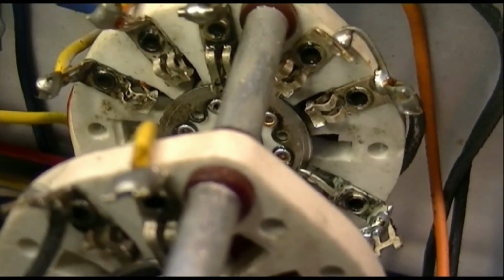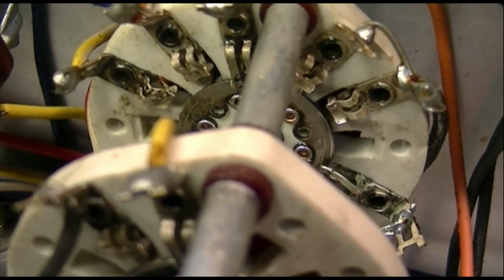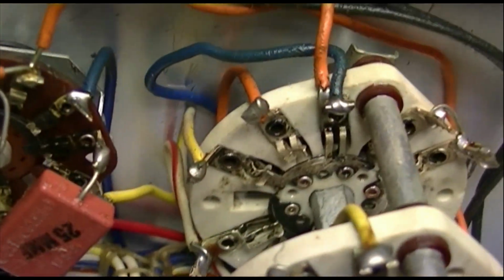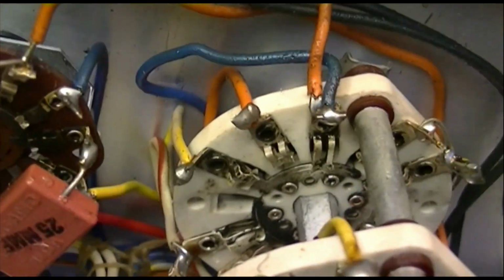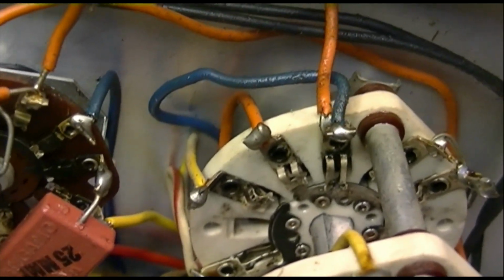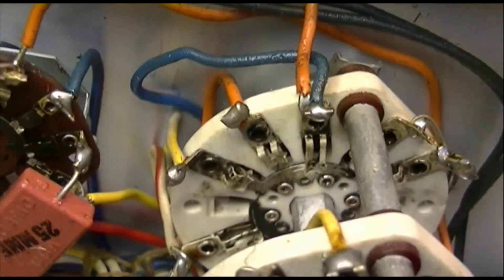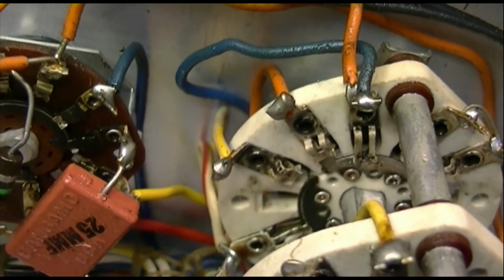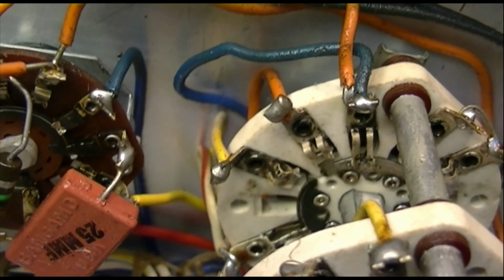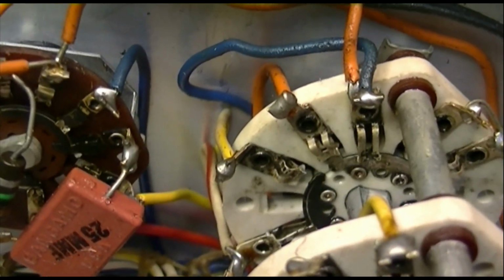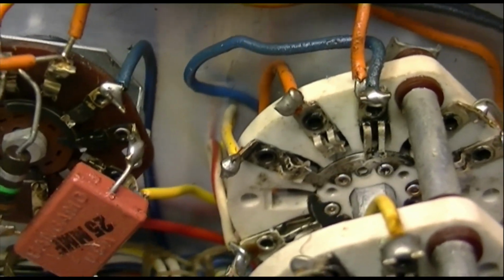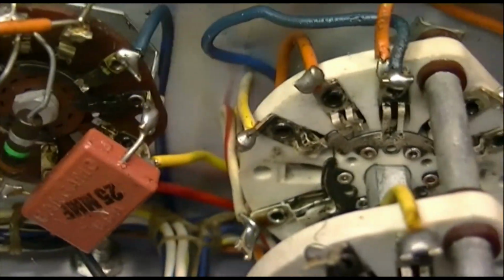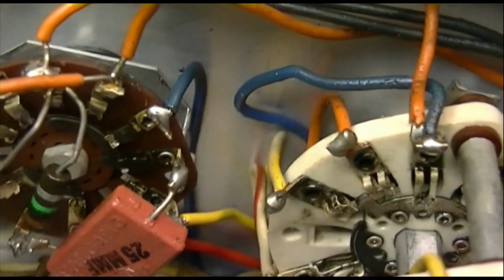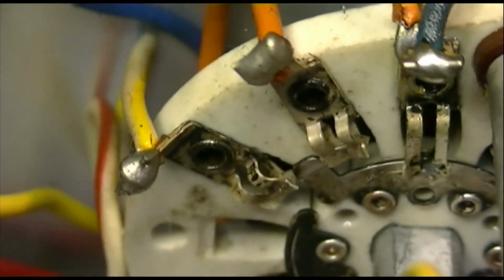Okay, here you can see the difference between a switch that's been cleaned some, these two halves of the wafer on the top, and then try to look—reflection is killing me here—but look at the section of the wafer down on the bottom that I haven't really gotten to yet, and you can see the difference. Now the contact is really just that little line that the wiper makes on there, or that the contacts will make, but in order to get any of it clean, you kind of have to get it all clean. But you can see that there's quite a bit of difference here from what it was.